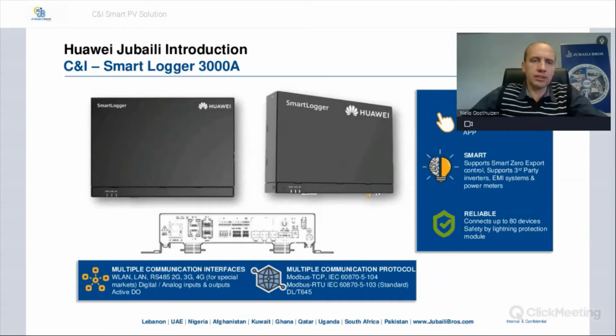Next one is on the C&I Smart Logger 3000A. So it's again on the communication side, but we're just upgrading a bit on communication. So the Smart Logger can support up to 80 devices. So it's got 3 inputs on each communication bus. Each communication bus can then take 30 inverters, so you can have 30 inverters on the first communication bus, 30 on the second one, but then on the third one you can only have 20.